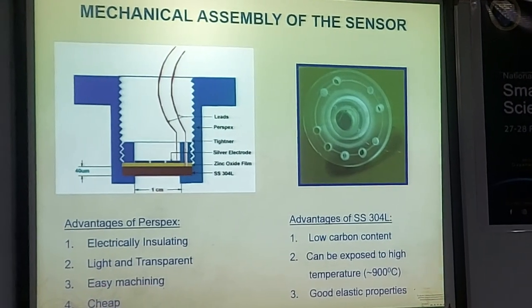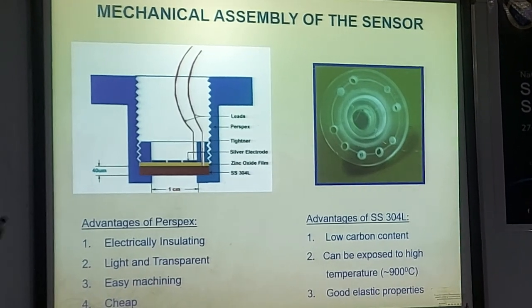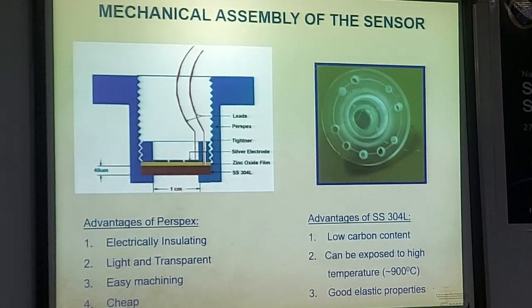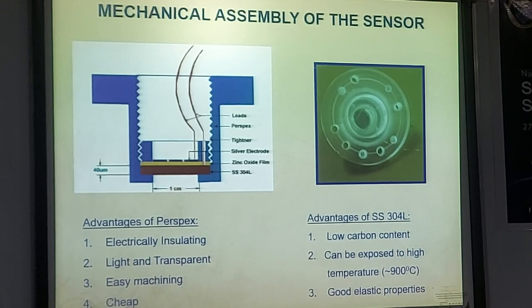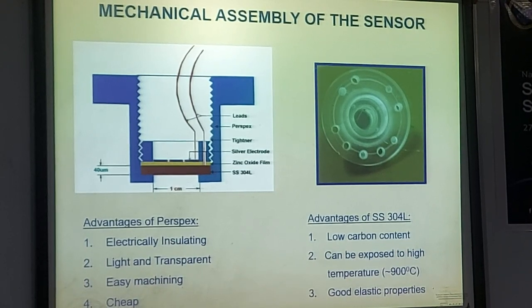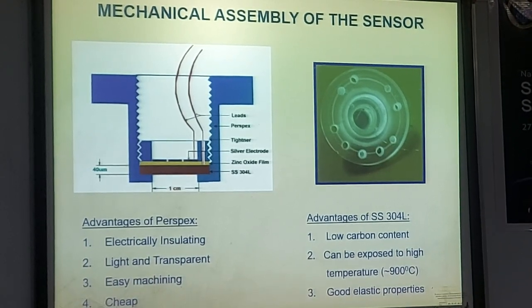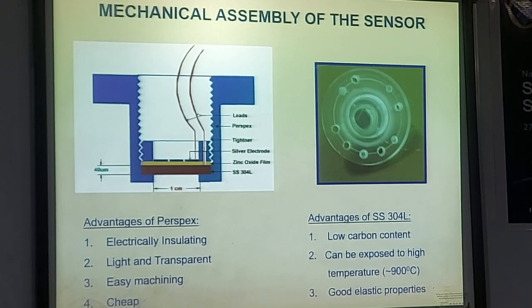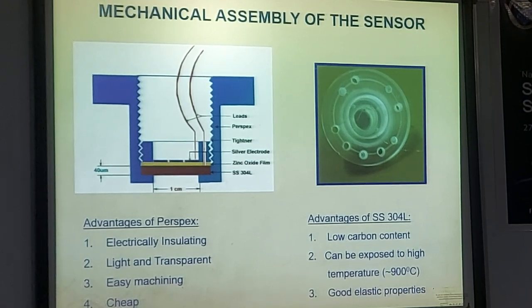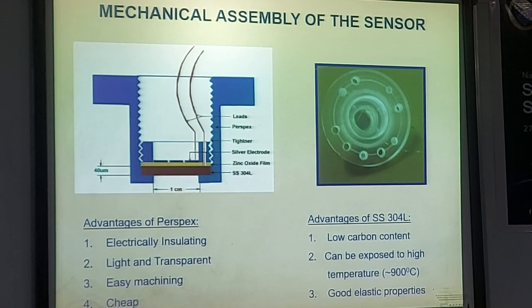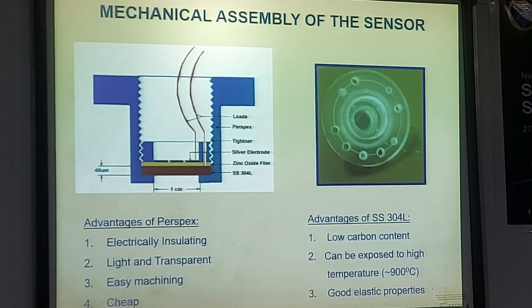And what is shown on the lower side here is a metal diaphragm, stainless steel diaphragm, and shown in yellow is a piezoelectric thin film deposited by sputtering technique. On top, there are metal electrodes to take electrical leads. So from the metal diaphragm one lead is taken, and from the top metal electrode deposited on the piezoelectric thin film, leads are taken out. And this is how the whole assembly looks, in the photograph.